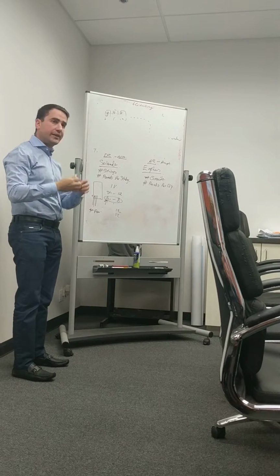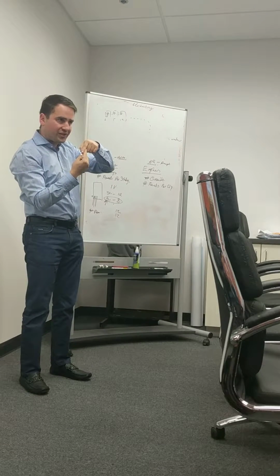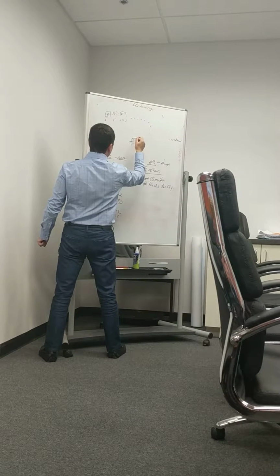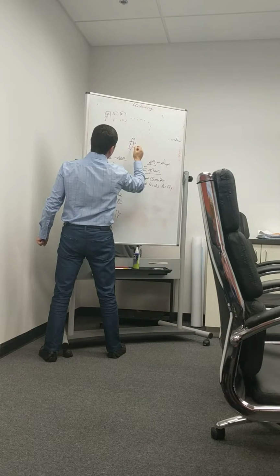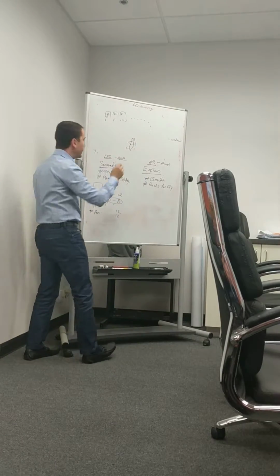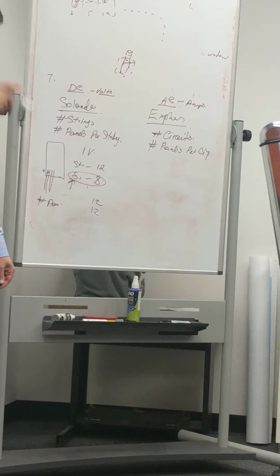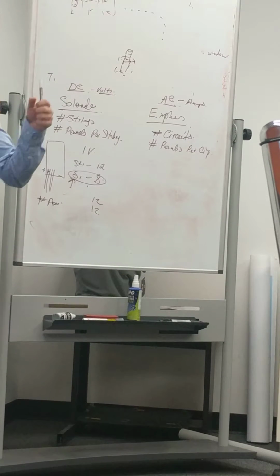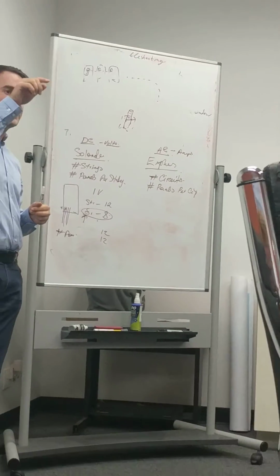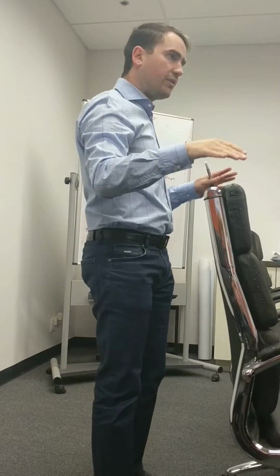When you do MC4 connectors, you look inside, you will see the metal is pushed. Because when you have an MC4, this is the plastic. Usually the metal needs to be here. When they don't do it right, the metal is like down here. So when you look, you will be able to see metal is pushed. And we can go to the warehouse and I will show you. When you see it's pushed, it means it doesn't have a direct contact. So you have to cut it and redo it again. MC4 connectors and MC4 crimpers, you must have when you're doing this job.